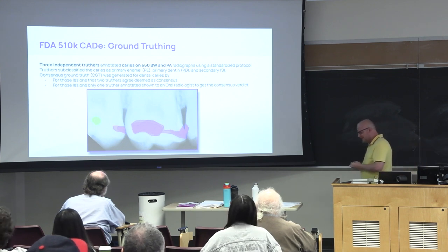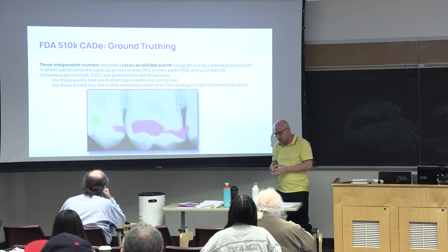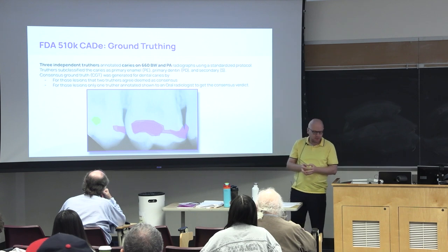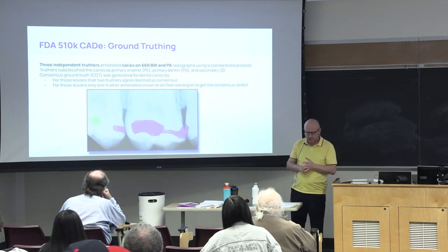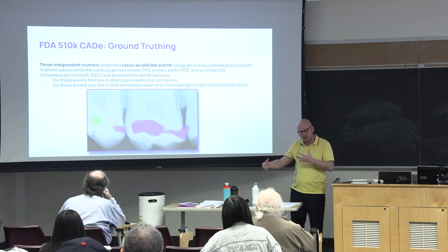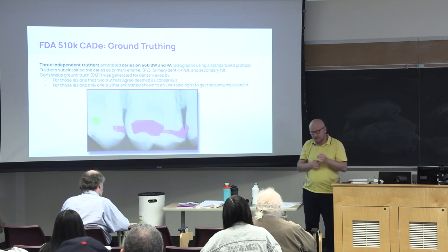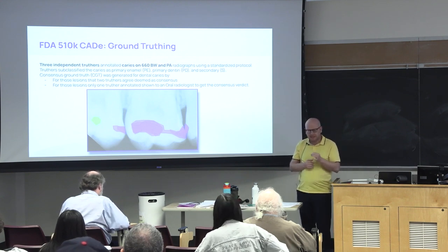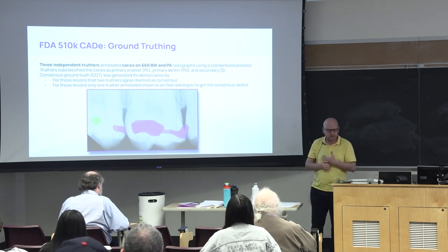And when constructing this ground truthing schema, we have taken into consideration the demographic distribution. This device is for patients aged 18 and above. Male, female, it has to be distributed. Age, still, 18 and above is not enough. We still need to distribute the age. Sensors: FDA giving a clearance doesn't mean it is cleared for every single sensor in that domain. It is specific to the sensors listed in the FDA clearance.